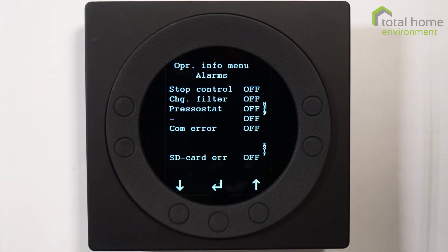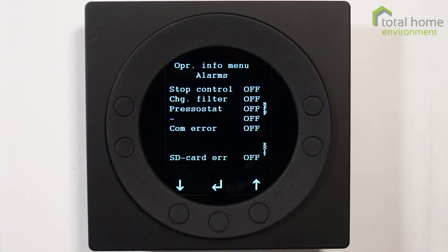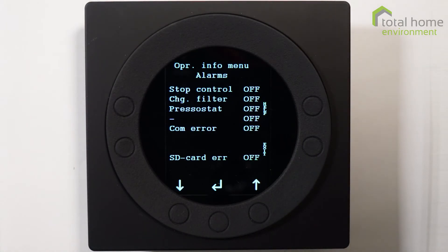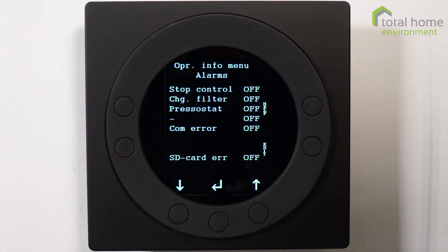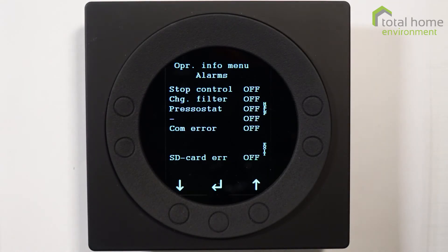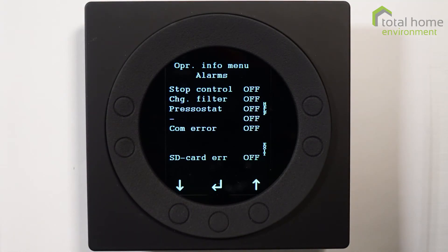If I go to the next page, that's a list of alarms and they're well worth knowing. Stop control is a function used usually in tenanted properties. If someone has failed to replace the filters when the filter alarm goes off, the stop control will stop the machine to prevent any damage. That occurs 14 days after the filter alarm has come on. We normally leave the stop control off, but under certain circumstances it can be activated and can be useful. Change filter alarm is obvious - the filter alarm function is a timer function. The factory setting is three months, but you can have it set to anything up to six months.